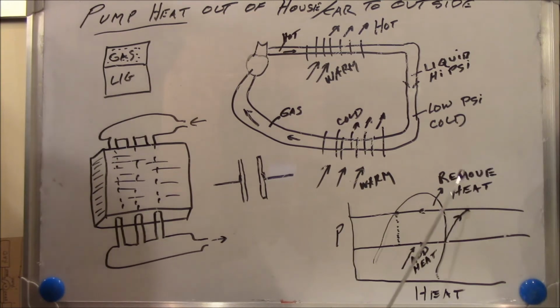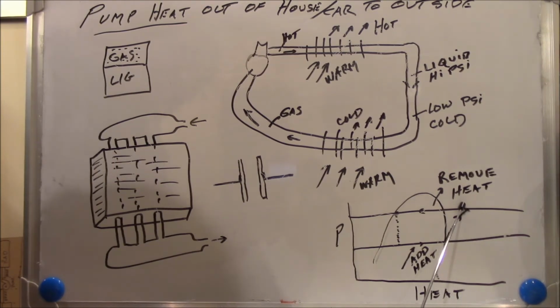Now what happens within the refrigerant, I'll show this on a pH chart: pressure, and this is enthalpy, but it's really heat. So you add heat as you go in this direction, you add pressure as you go in this direction. So when this pump pumps the pressure up, it pumps it along this line from this pressure to this pressure, and it gets very hot.